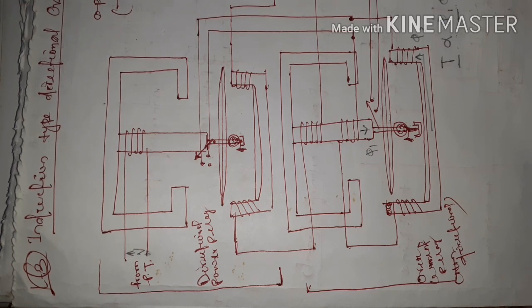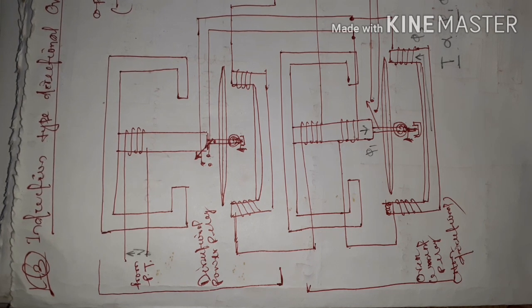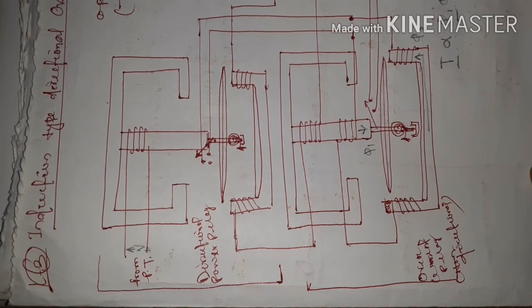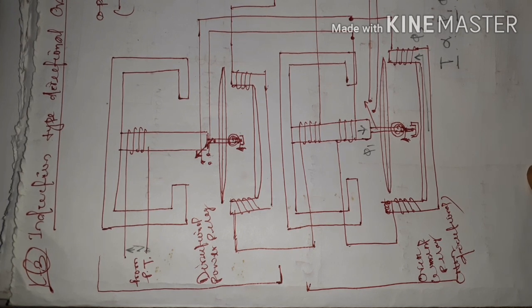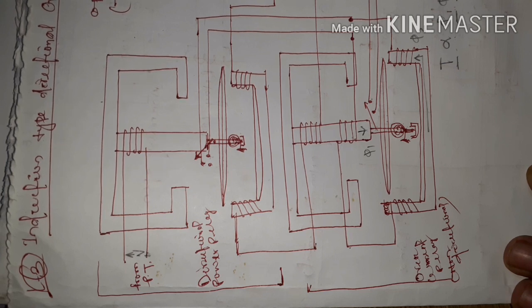Hello students, today I will discuss about induction type directional overcurrent relay. This type of relay is the combination of directional power relay and non-directional overcurrent relay. The function of non-directional overcurrent relay is that when the magnitude of fault current exceeds the predetermined value it is able to operate, whereas the function of directional power relay is that when the flow of electric current or power is in a specified direction.